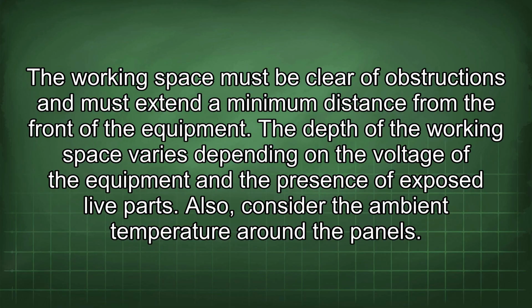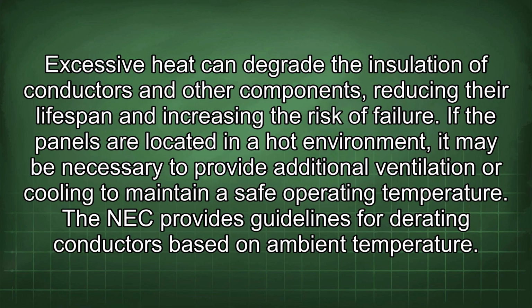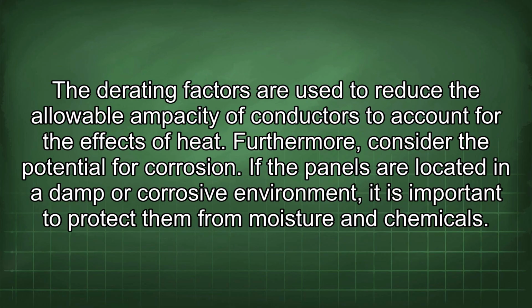Also, consider the ambient temperature around the panels. Excessive heat can degrade the insulation of conductors and other components, reducing their lifespan and increasing the risk of failure. If the panels are located in a hot environment, it may be necessary to provide additional ventilation or cooling to maintain a safe operating temperature. The NEC provides guidelines for derating conductors based on ambient temperature. The derating factors are used to reduce the allowable ampacity of conductors to account for the effects of heat.